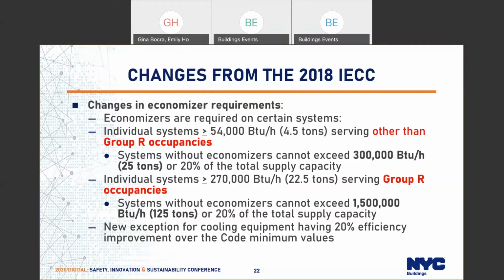Essentially, any cooling system greater than 54,000 BTU must have an economizer. And then for buildings other than Group R occupancies, the total system capacity without economizers, even if they're less than 54,000 BTU, cannot exceed an aggregate capacity of 300,000 BTU, or 20% of the total supply capacity. So that's what the 2016 code said, and that is still the same for the 2020 code in other than Group R occupancies. Now the change comes in Group R occupancy buildings, so your residential, your hotel.